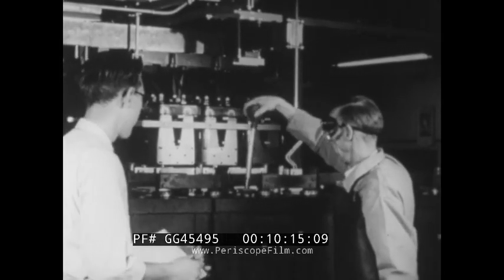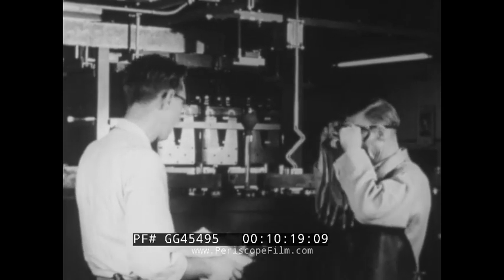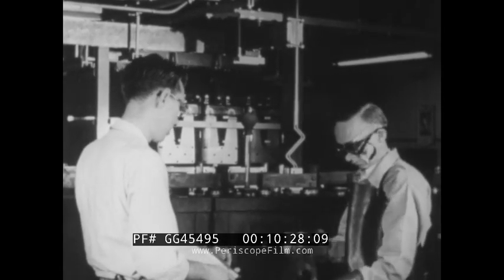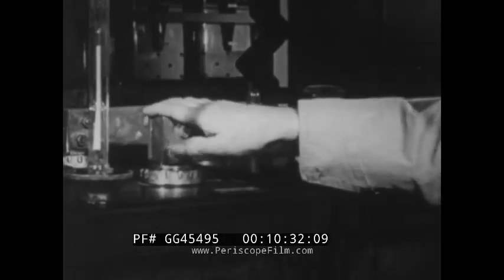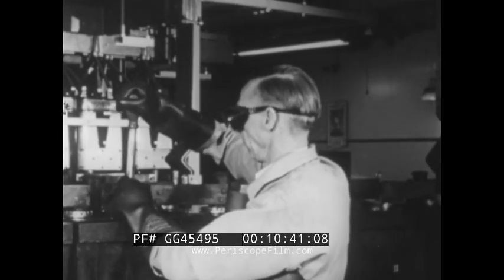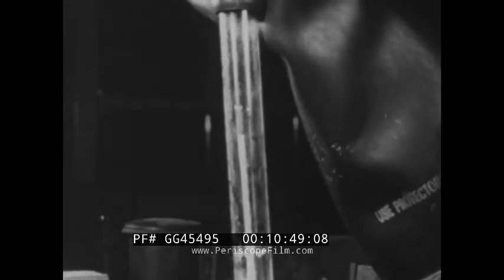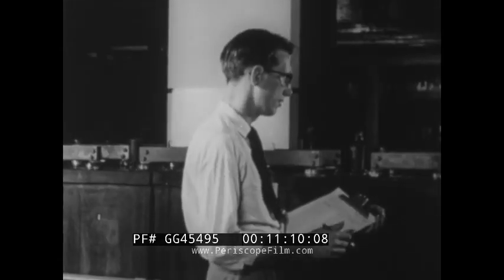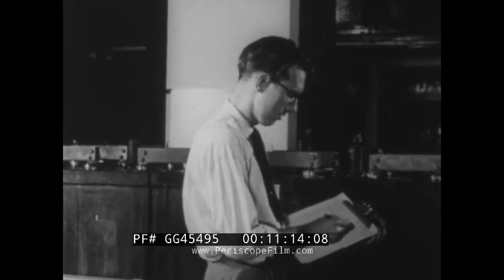The taking and recording of readings is an important battery maintenance function. Note the protective equipment used by the man who will take the hydrometer reading. Before starting the job, static electricity is discharged by touching an intercell connector near the grounded end of the string. The hydrometer must be held vertical. The electrolyte level in the barrel must not be too low or too high. Now this will give an accurate reading. The maintenance man must always remember that the storage battery can be explosive, even with the new explosion-proof features.